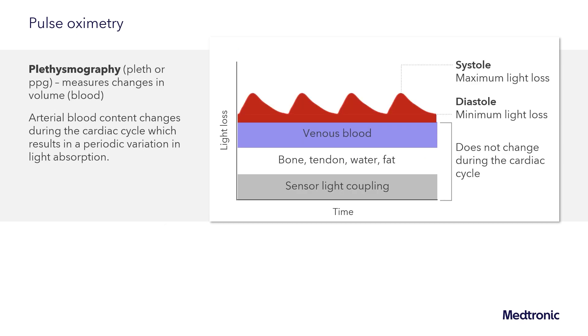We do that by focusing in on the pleth. The pleth is created because arterial blood content changes during the cardiac cycle. There are many things that can cause light to be attenuated as it travels from the LED to the detector — how the sensor is constructed, what other tissue is present such as bone, tendon, water, or fat, as well as the blood, and how much venous blood is present. However, it is only the arterial blood that is changing in time. As blood is pushed into the arteries, there is an increase in light loss due to increased absorption, and as it is squeezed out, there is a decrease in light loss due to decreased absorption.